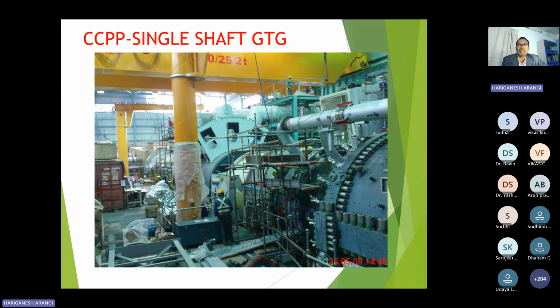There will be a generator in the middle. On one side the gas turbine will be connected, and on the other side the steam turbine will be connected. When the steam is not there, only the gas turbine and the generator will be operated, and power generation will be around 240 to 250 megawatt. After the steam generation, the steam turbine gets coupled automatically with respect to the triple S clutch. Then the steam turbine also rotates, and that also gives add-on power. So it is a capacity of a 385 megawatt unit.